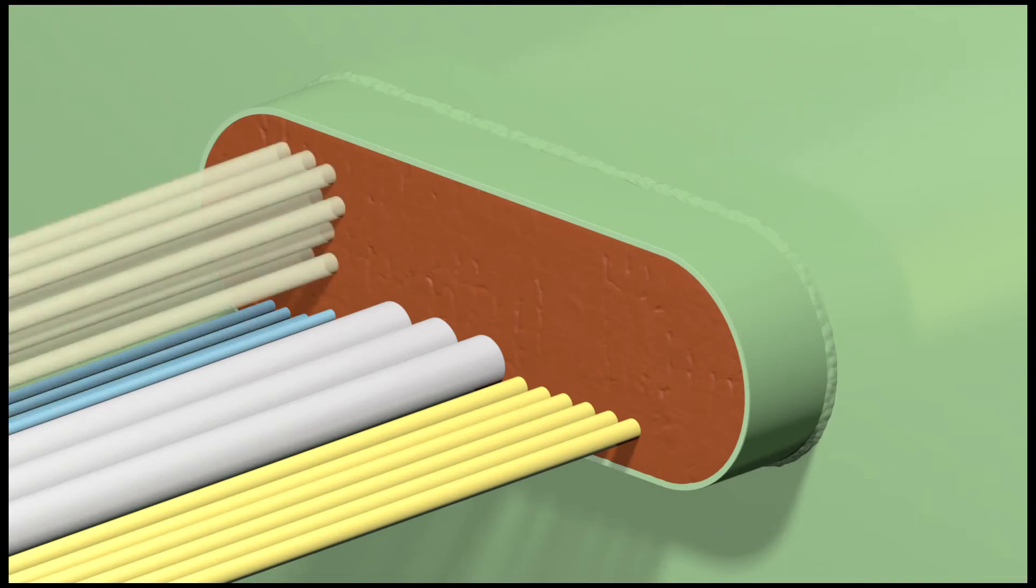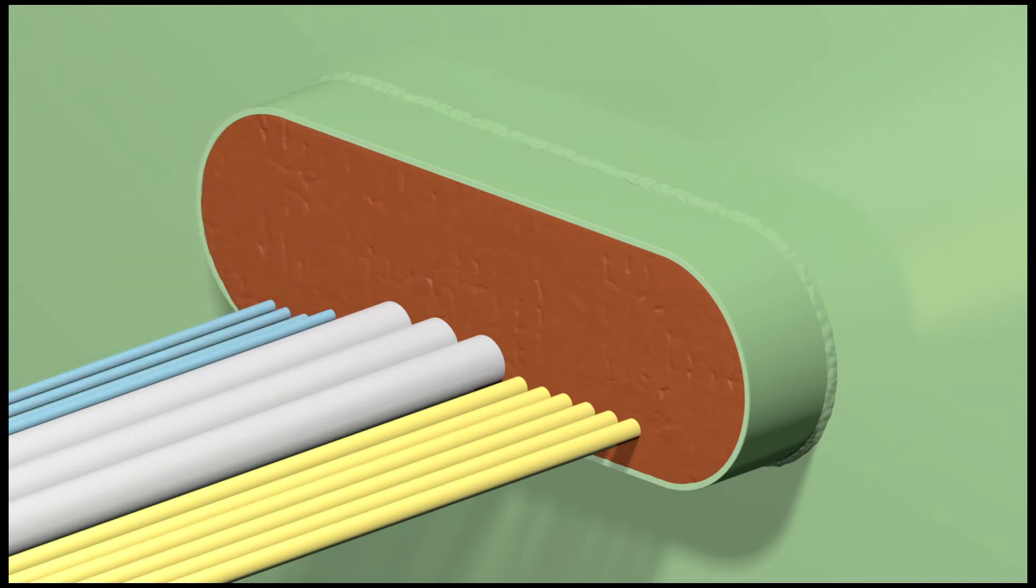Especially with a high cable fill, a last check should be made to ensure that the sealant layer is pressed down tightly. Air enclosure in the sealant layer should be prevented during finishing because this would have a negative impact on the performance of the sealant layer under fire exposure. The final surface can be smoothed by hand.